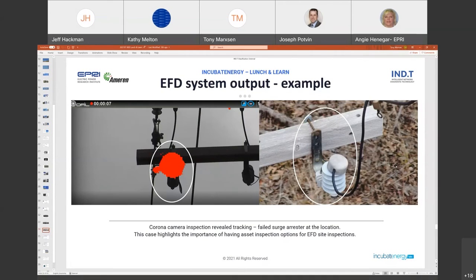The other thing I would note, and we don't have a slide on it, is that on this same section they identified a distribution transformer. Again, the sensors are not on the distribution, they're on the subtransmission, but the IND system identified the exact location of a transformer that had a bad connection at the low voltage terminals. The system was able to detect that, and they were able to tighten up those connections.